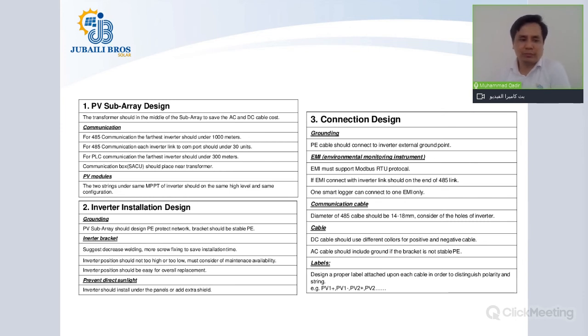We spoke of the different orientation of solar modules. We spoke of the grounding, the inverter bracket earthing, preventing direct sunlight to the inverter, the grounding on the inverter itself, and the points that you have the option of, the weather monitoring instrument, which is the weather station. Normally, you should be using a Modbus RTU protocol based EMI if you're using an unlisted weather station.